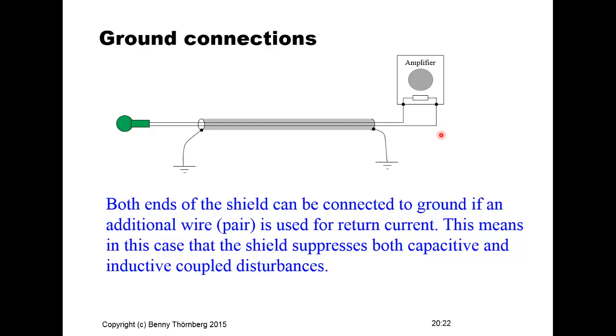Alternatively, if an additional return wire is used — making a pair of wires — both ends of the shield can be grounded, suppressing both capacitive and inductive coupled disturbances. A differential amplifier input is used, with one wire for the signal and one for the return current. Suppression is even better if these wires are twisted.